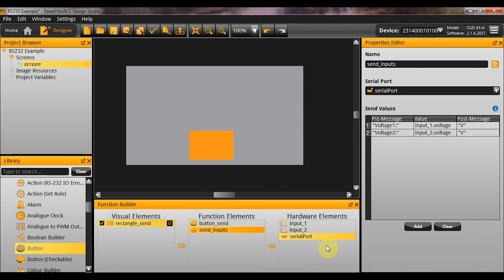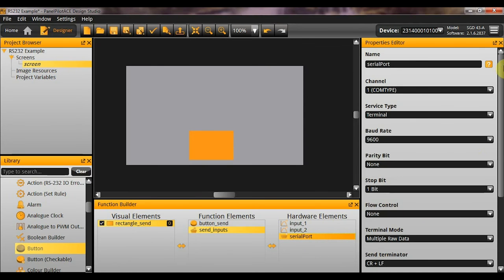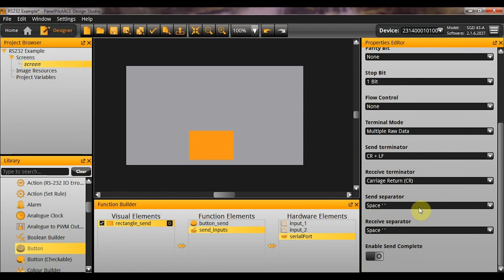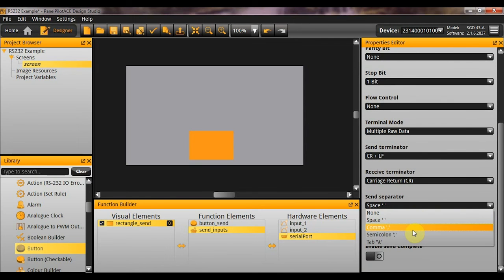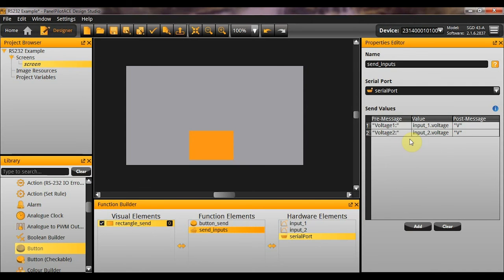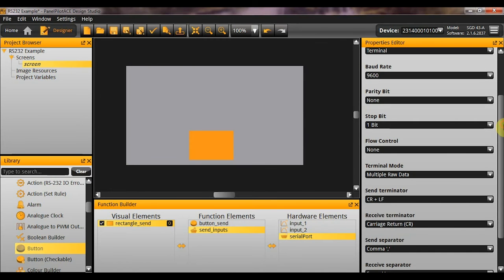Just to give you a quick rundown of the format that these are going to be sent in. So, you push that button. And then it will send the first value. So, voltage 1, the actual value, the V letter for the units. Then it will send our RS232 separator. You can see in here, our send separator. I should be more specific. That is a space. I actually want it to come out as a comma. Then it will send the next value. So, voltage 2, the value, followed by volts. And then, because there are no more values, it will send the send terminator. We have got carriage return line feed here.